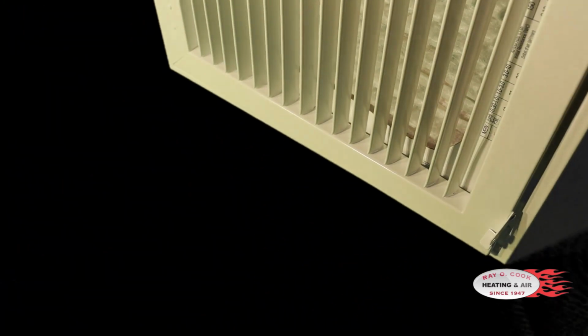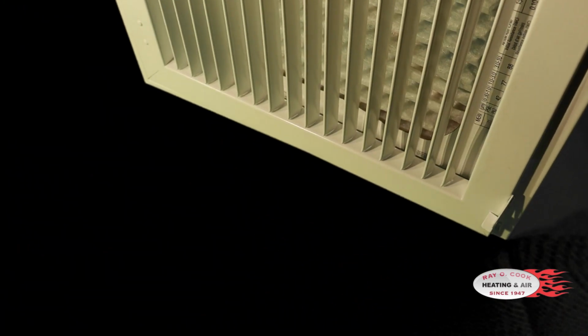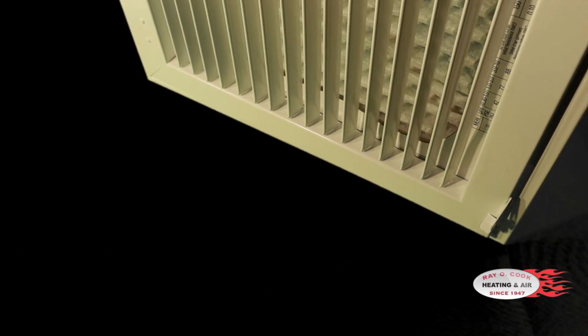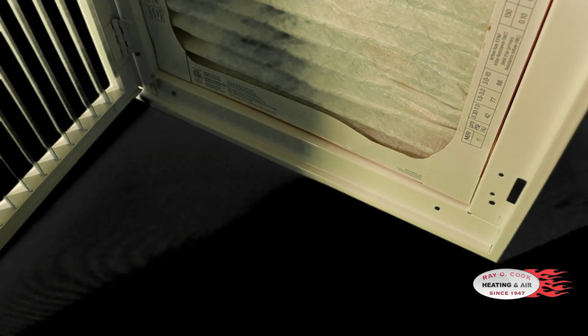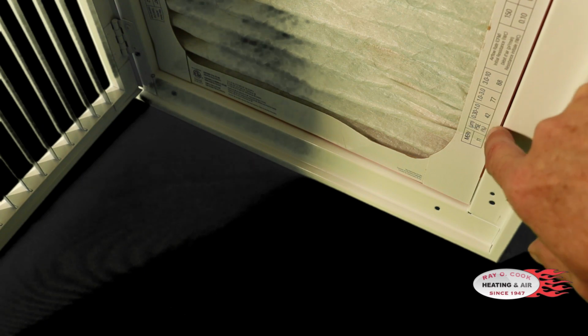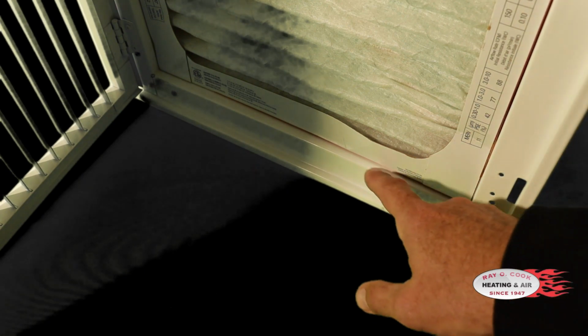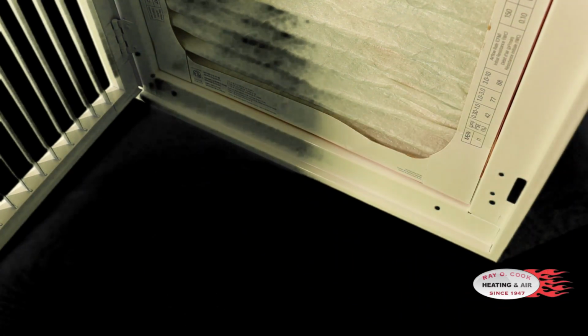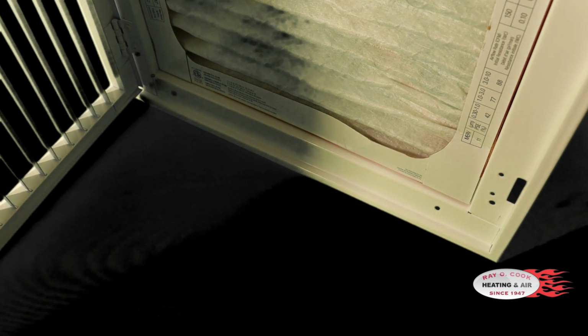So the fan, whether it's in the attic or in the garage or wherever the fan that moves the air through your ductwork is located, it's sucking air through this grill to get the air that it needs to cool your home. So when you look at these filter grills, you can clearly see the gap here. There's a gap all the way around here. Those filters are not sealed 100% airtight.